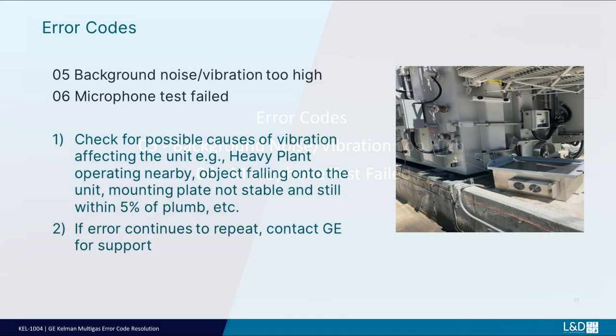Error code 05: Background noise or vibration too high. Error code 06: Microphone test failed. Check for possible causes of excessive vibration affecting the unit — for example, heavy plant operating nearby, objects falling onto the unit, the monitor mounting not stable, or the monitor still within 5 degrees of plumb triaxially.